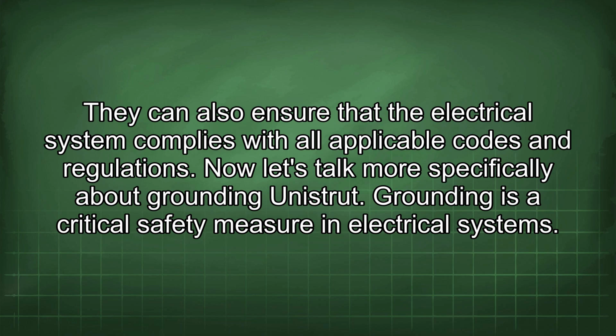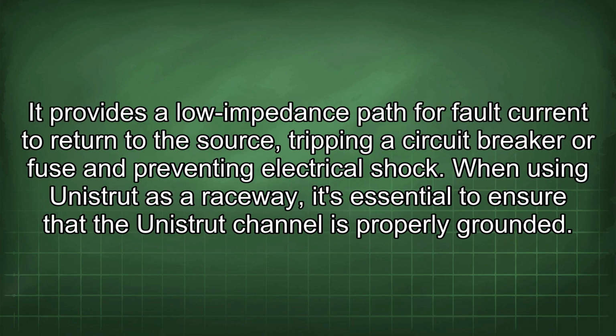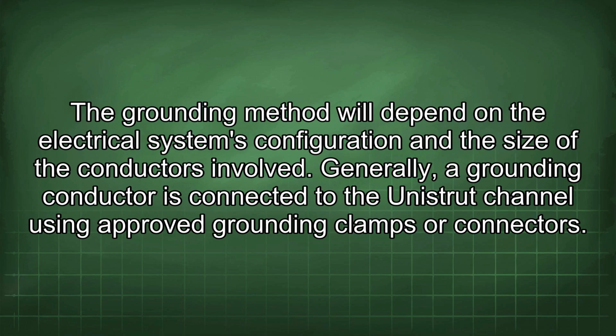Now let's talk more specifically about grounding Unistrut. Grounding is a critical safety measure in electrical systems. It provides a low impedance path for fault current to return to the source, tripping a circuit breaker or fuse and preventing electrical shock. When using Unistrut as a raceway, it's essential to ensure that the Unistrut channel is properly grounded. The grounding method will depend on the electrical system's configuration and the size of the conductors involved.